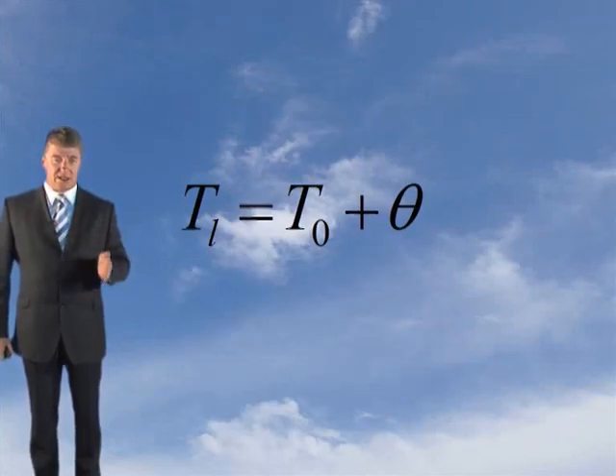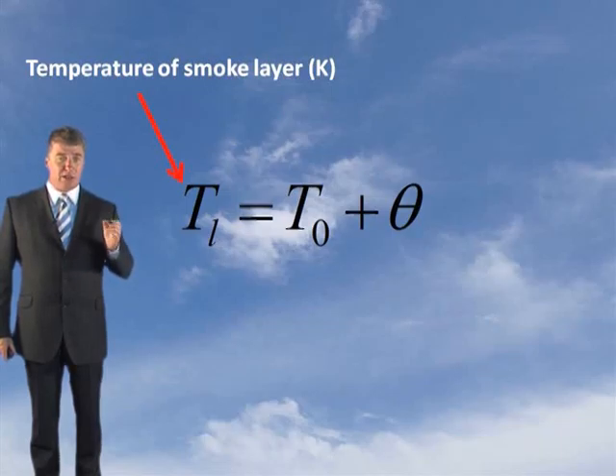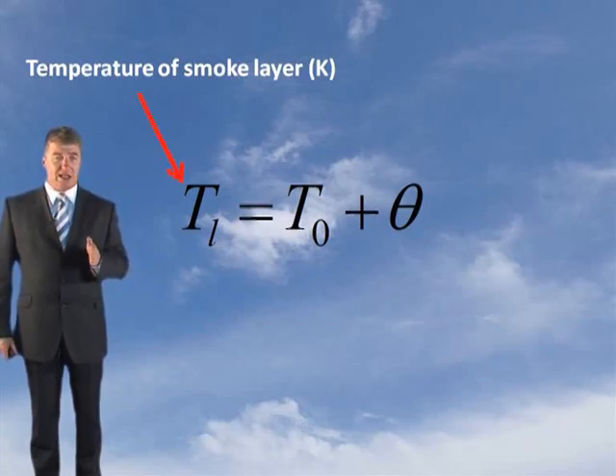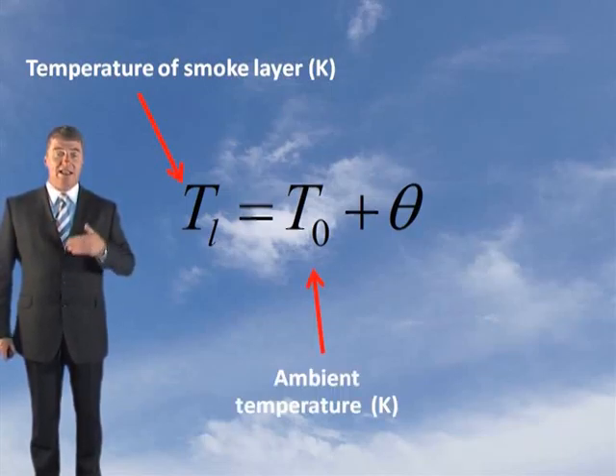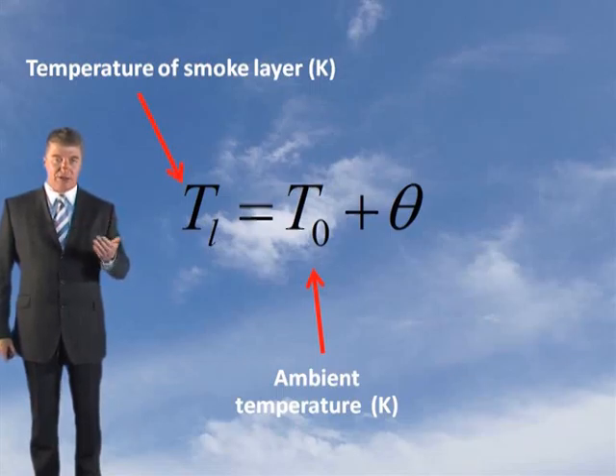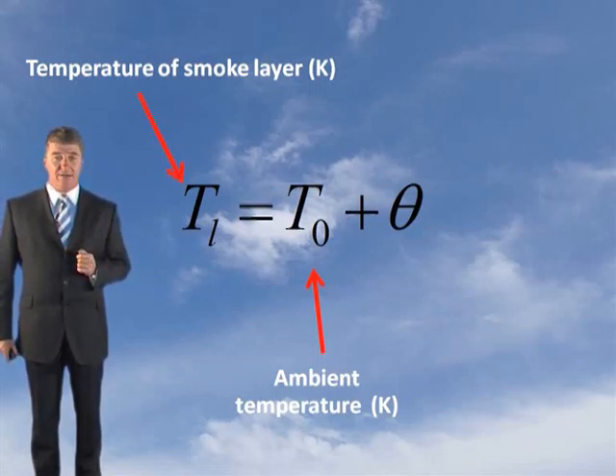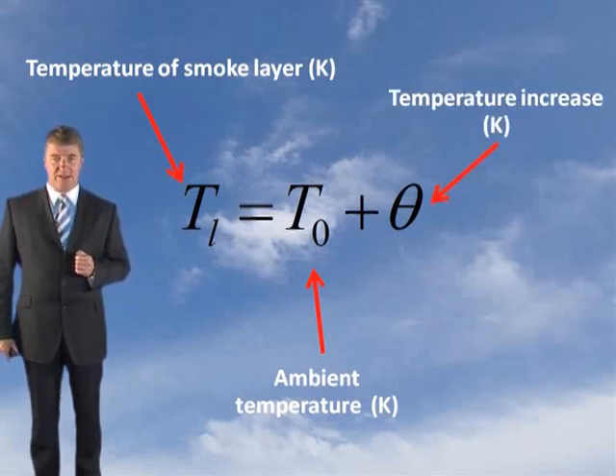Now we need to determine the absolute average temperature of the smoke. The formula to apply is: TL equals TO plus theta, where TL is the absolute average temperature of the smoke layer, TO is the ambient air temperature which is normally taken as 288 degrees Kelvin, and theta is the temperature increase.